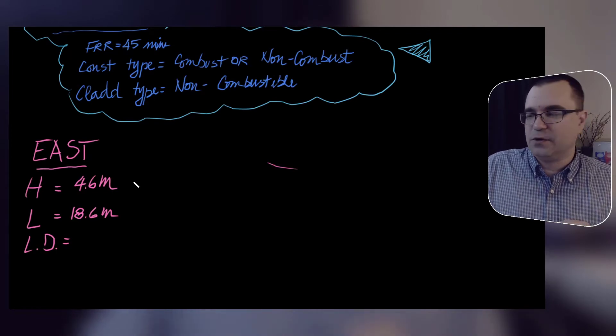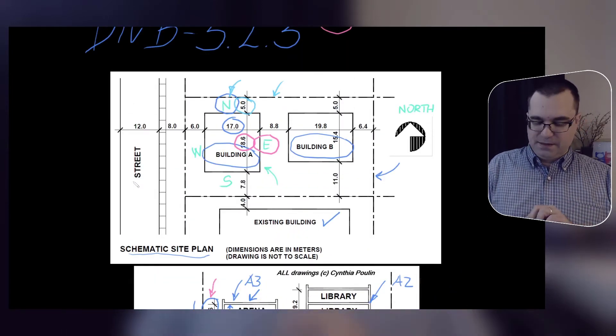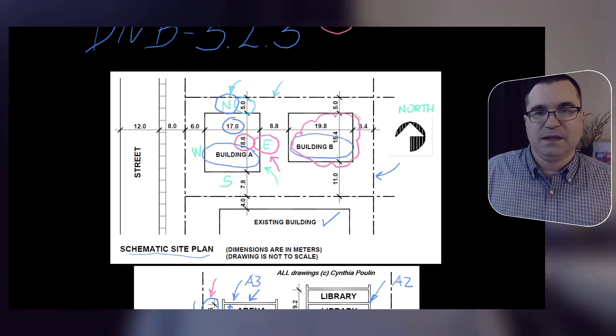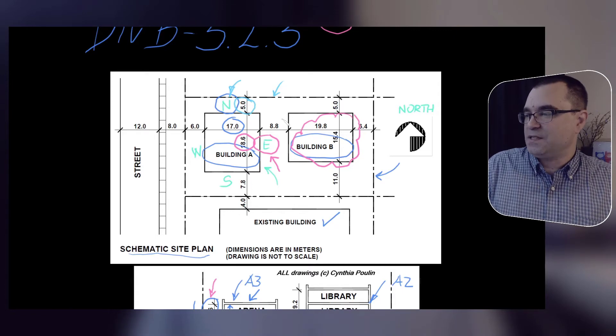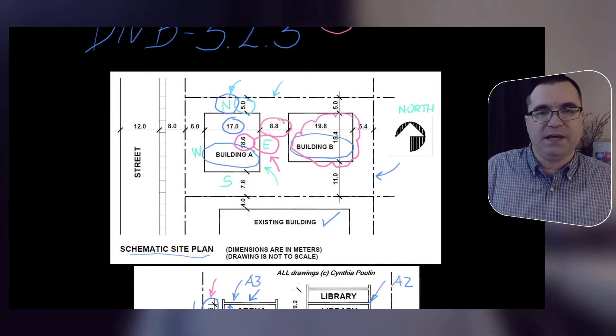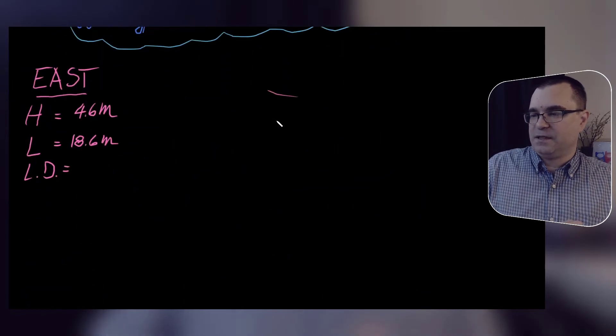What about the limiting distance? Well, in this case, if you go and read the definition for limiting distance, you find that since the east face is facing another building right here — building B — the limiting distance is halfway between those two buildings. That means we're going to take this distance, 8.8, and divide it by two for the limiting distance: 8.8 divided by 2 equals 4.4 meters.